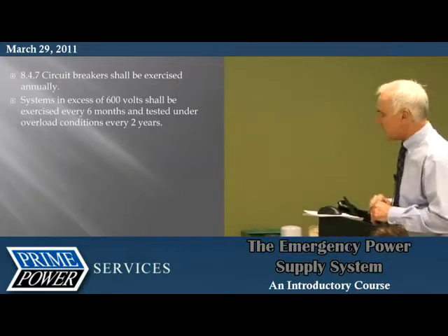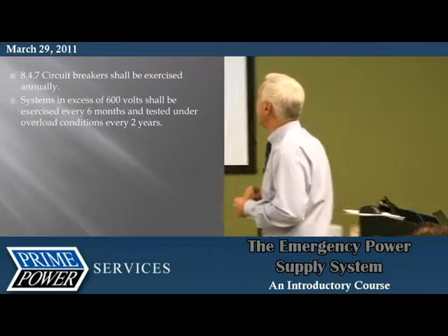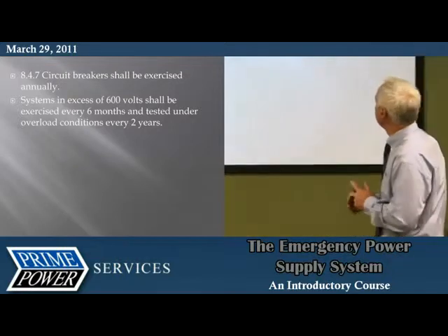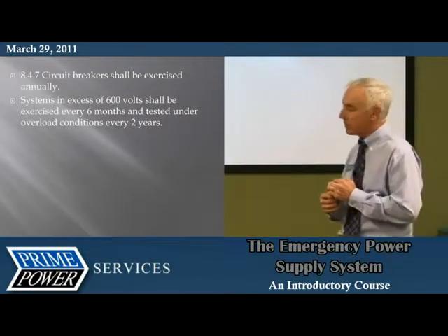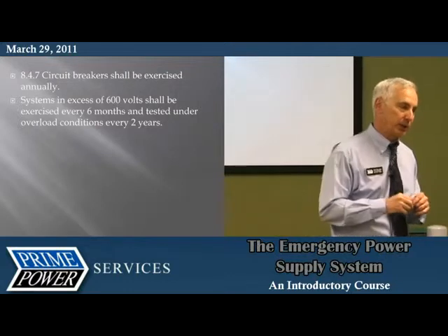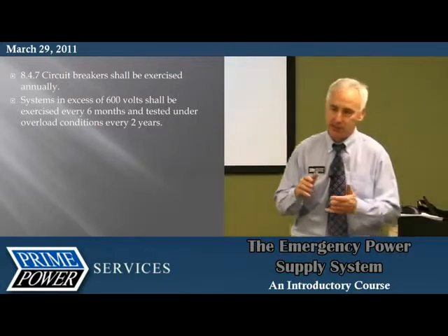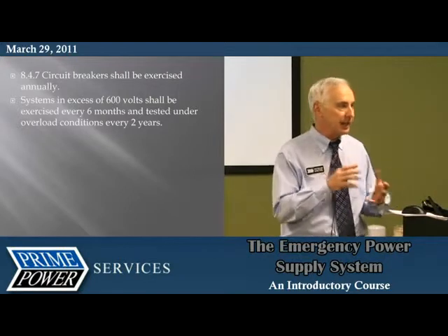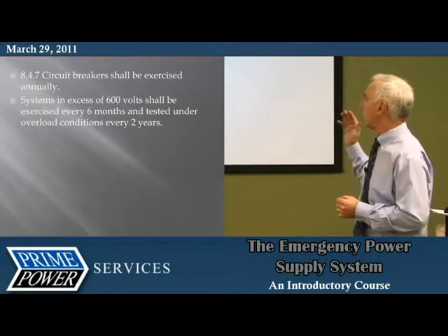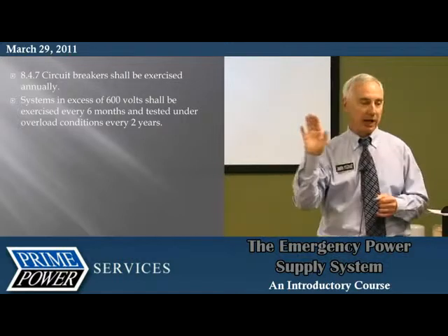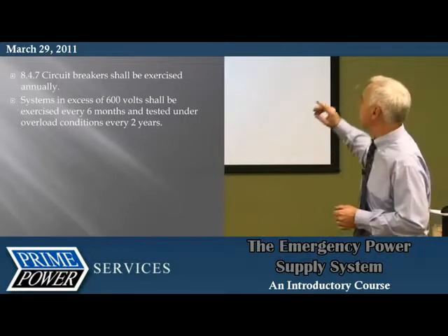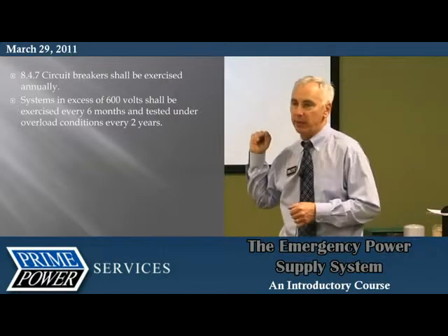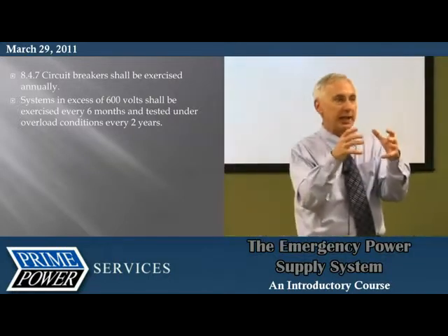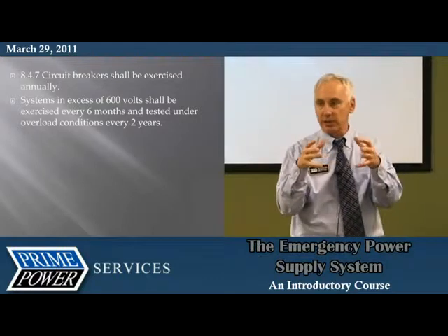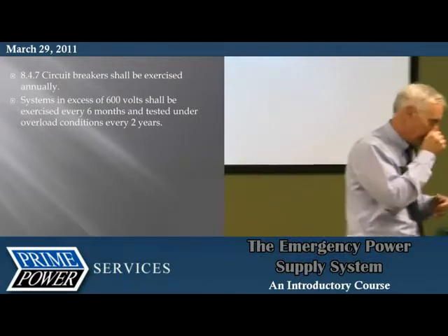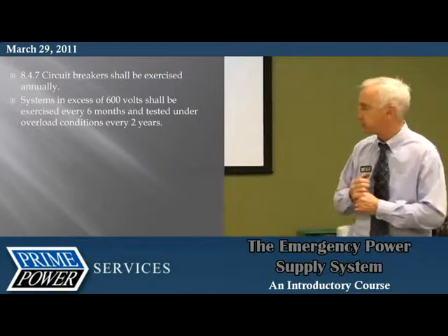So systems in excess of 600 volts shall be exercised every 6 months and tested under overload conditions every 2 years. So the medium voltage systems, the high voltage systems, that's the 4160, the 138, these type systems have got a little more onerous requirements. They have to be operated every 6 months, and when they say overload conditions, what they're talking about on a medium voltage breaker is that there will be a protective relay that actually governs when it opens and closes during a fault. That has to be calibrated. That's specifically what they're talking about.